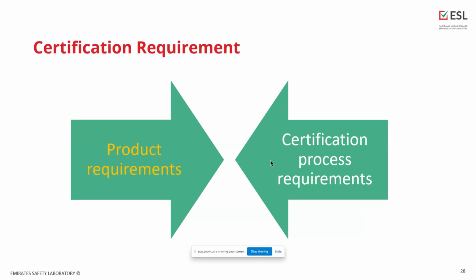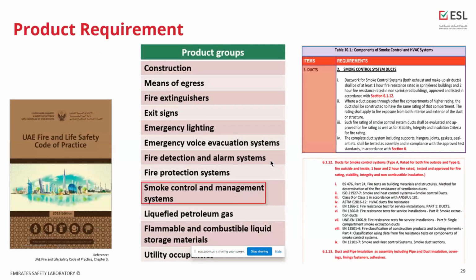For the product requirement, this normally comes from your targeted market and your building regulations. For example, in the UAE Fire and Life Safety Code, the local requirement in the UAE, in Chapter 10 we can find all the requirements for the smoke control system in the code. Also, we can see here there is a specific requirement for the system, what the requirement is for the smoke control system, and also what the applicable standards recognized by the code are.